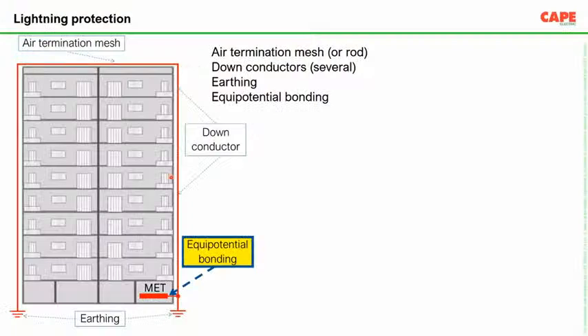Lightning protection, there are two different subjects. One is external protection, the next one is internal protection. In fact, lightning protection is the most interesting subject for me. External protection means protecting a building or a structure. So here, what I am showing in this particular picture, the red one is nothing but the air termination mesh at the top, the down conductors, and the earthing. So here, for explosive areas and areas wherever sensitive things are there, we are not supposed to make independent or separate vertical rods. We are supposed to make a ring earth. Ring earth means a conductor all around the building as a ring.